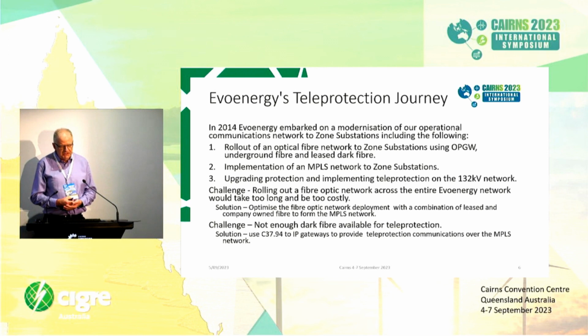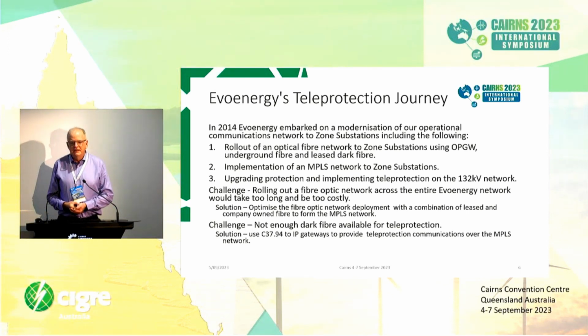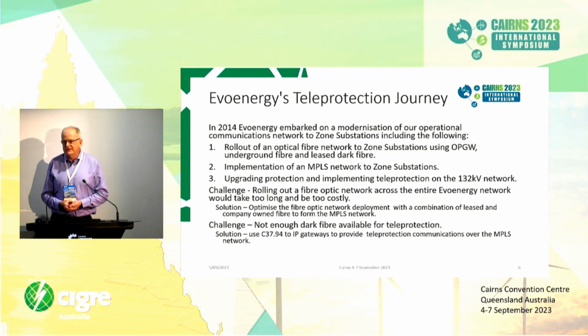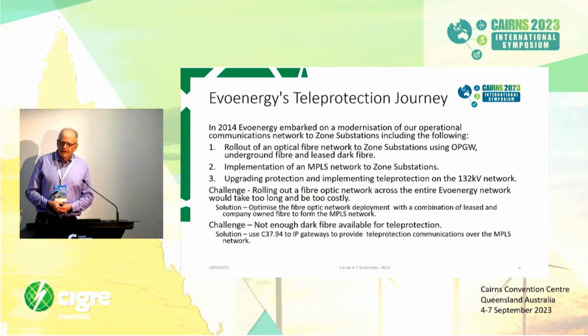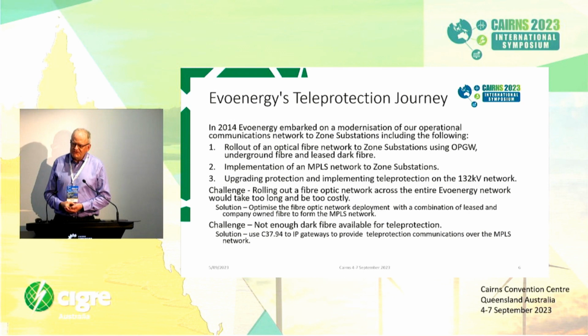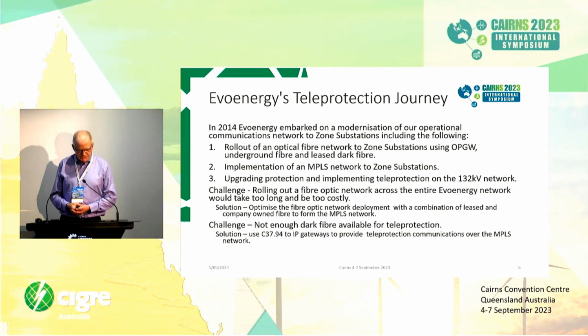So, a bit about our teleprotection journey. We embarked on this technology upgrade in 2014. We started by realising that protection clearance times weren't up to scratch, so we needed to provide communications enabled and accelerated protection systems across the transmission network. We started by rolling out optical fibre. Obviously, optical fibre is a large investment. We couldn't roll out the fibre quick enough across our entire network to meet the requirements of the protection, so we also augmented that with some leased fibre and also some underground fibre that we already had. On top of that, we've implemented an MPLS IP network to all the zone substations.